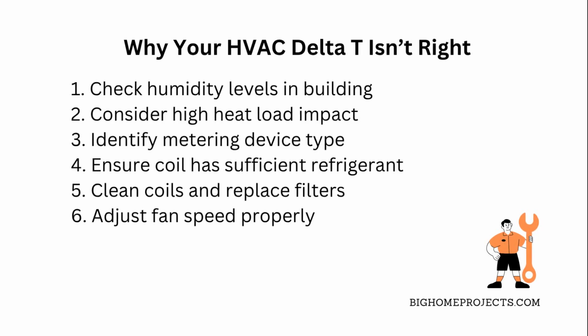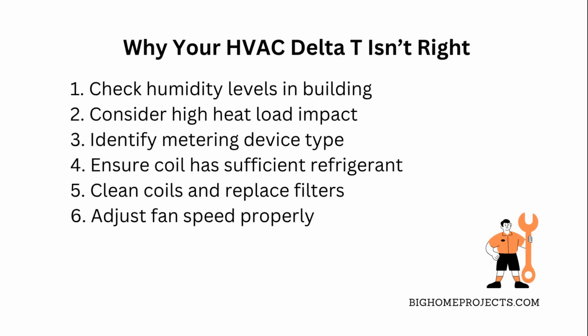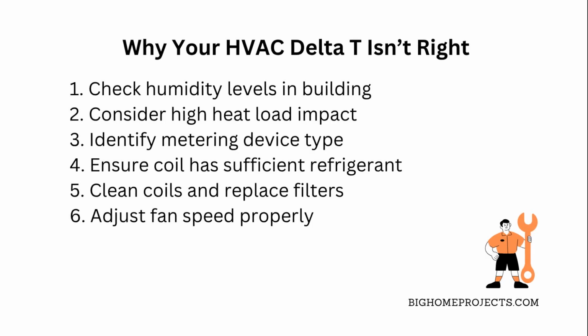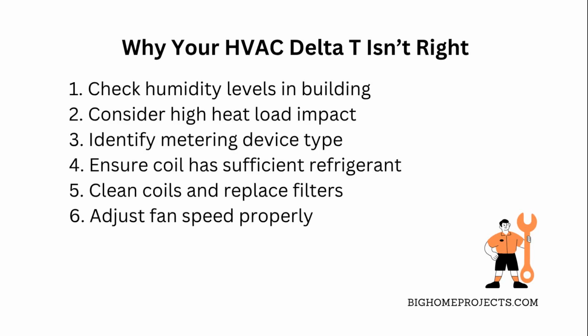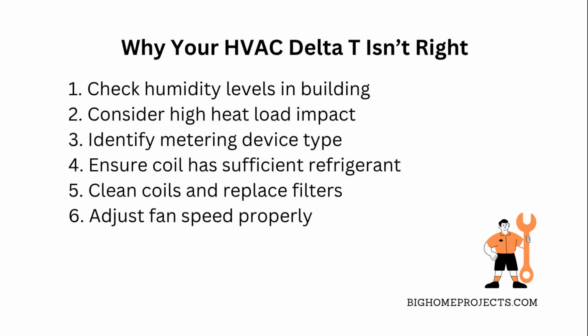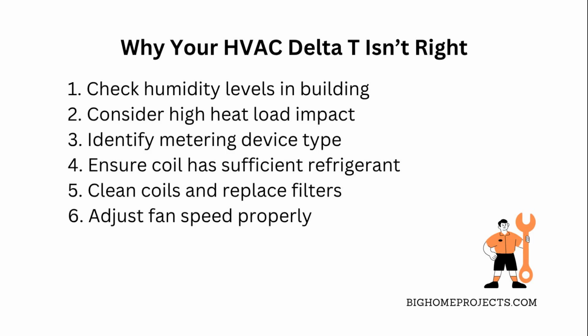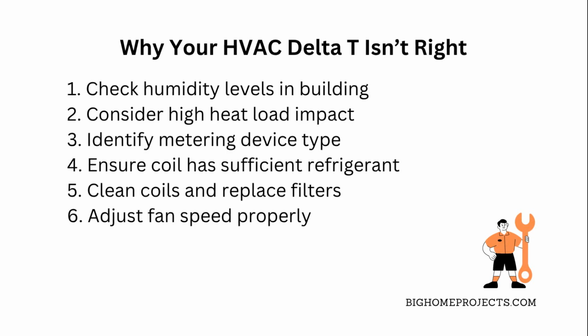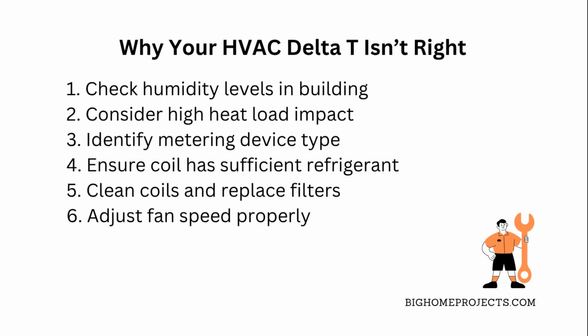First off, high humidity in the building can throw off how the system cools because it's got to work harder to remove moisture from the air. Then, if your space has a high heat load, like lots of people, electronics, or sunlight, that can push the system beyond what it usually handles, so the Delta T won't be what you expect. Also, some HVAC units use pistons or capillary tubes instead of more common expansion valves, and that changes how refrigerant flows and affects Delta T.